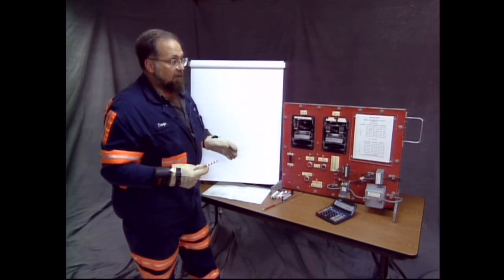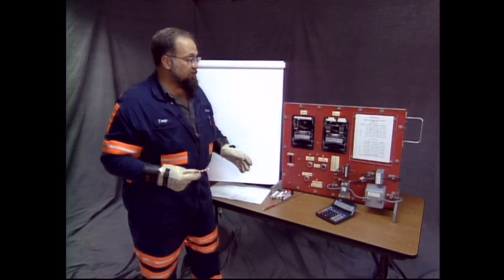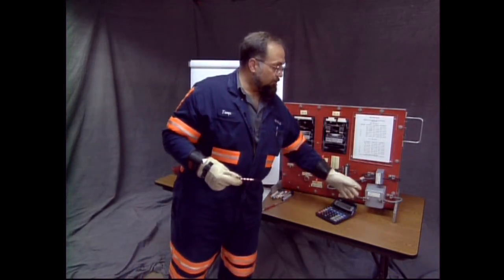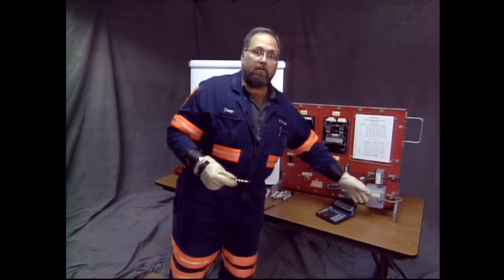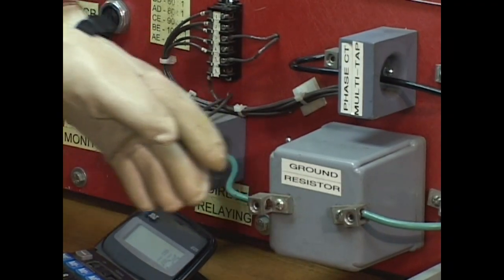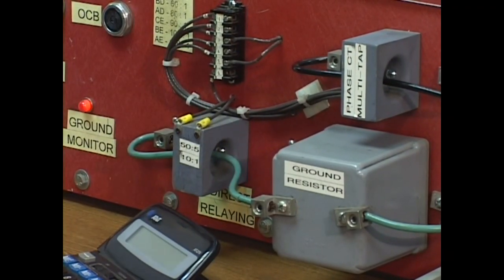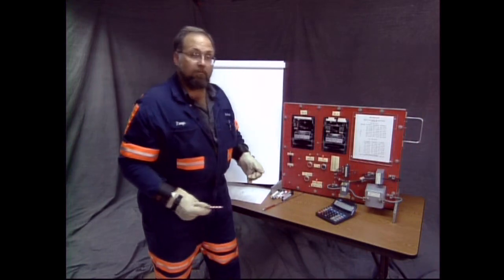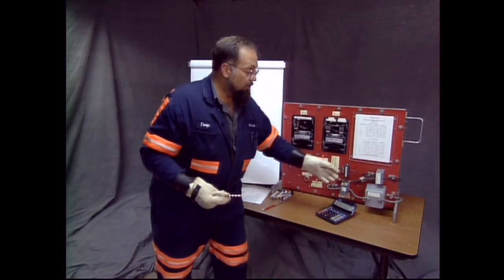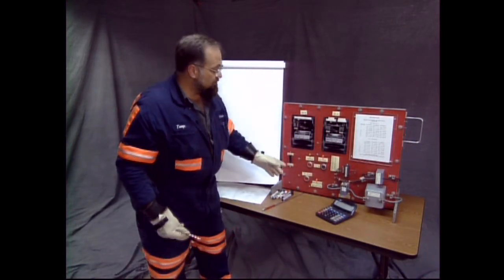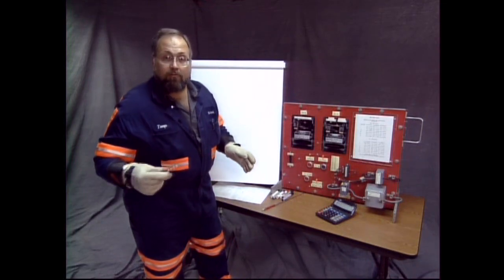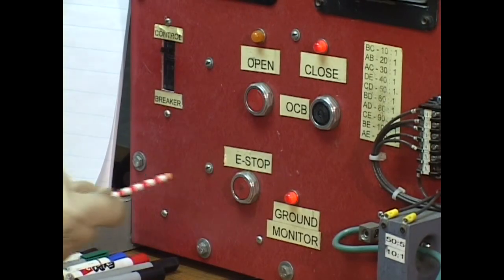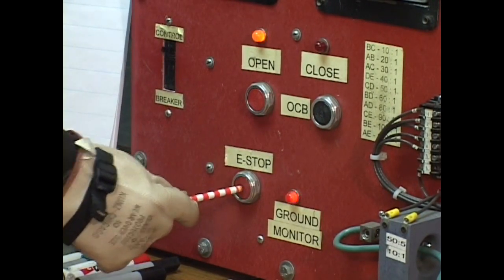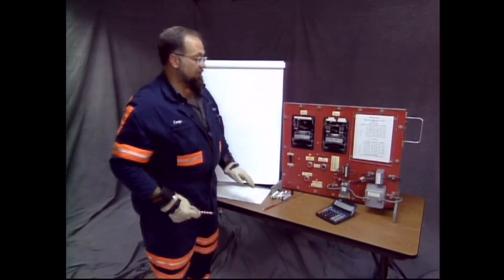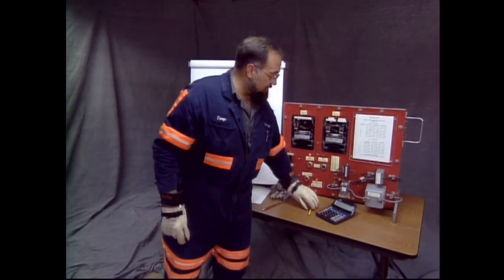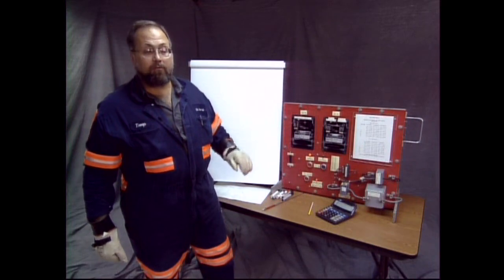You're using the E-stop. It's a tool, just as if you were going to use your meter, your multitester, to check the ohmic value of the ground resistor. You wouldn't say, I'm checking my own meter. You're using the ohm meter as a tool to check the value of the ground resistor. You're going to use the E-stop to check ground continuity. So you're going to operate the E-stop at the furthest point, and your breaker opens. And that concludes the testing of the high voltage circuit breaker relays.